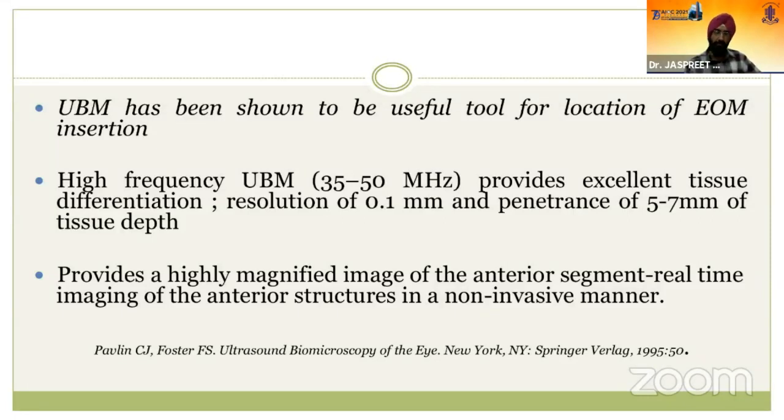It's basically a 35 to 50 megahertz probe. We have a 10 megahertz probe as well. It has excellent tissue differentiation, a resolution of 0.1 millimeter, and good penetrance. It provides a magnified image of the anterior segment, which is real time, in a non-invasive manner.